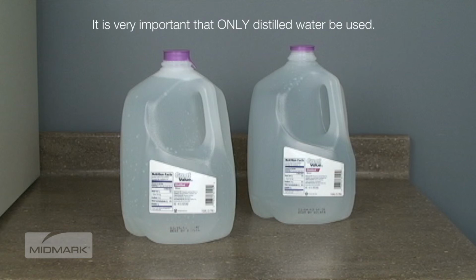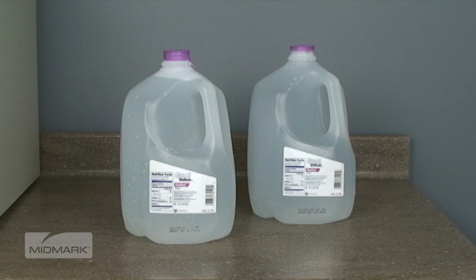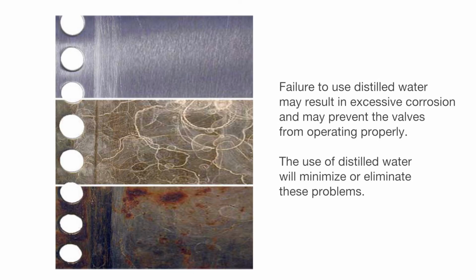It's very important that only distilled water be used. Since the autoclave operates with high water temperatures, any minerals dissolved in the water will form mineral deposits. Failure to use distilled water may result in excessive corrosion and may prevent the valves from operating properly. The use of distilled water will minimize or eliminate these problems.